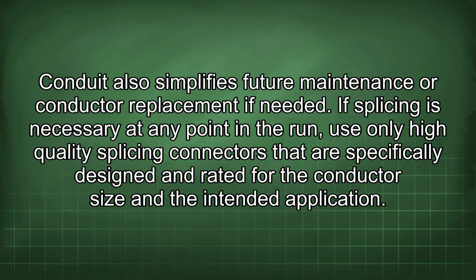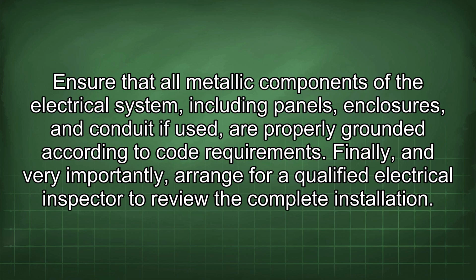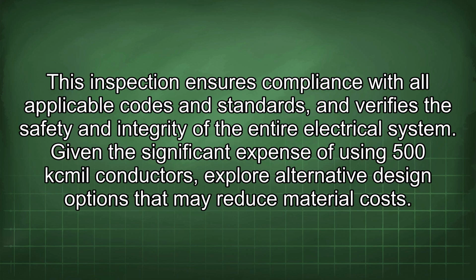If splicing is necessary at any point in the run, use only high-quality splicing connectors that are specifically designed and rated for the conductor size and the intended application. Ensure that all metallic components of the electrical system, including panels, enclosures, and conduit if used, are properly grounded according to code requirements. Finally, and very importantly, arrange for a qualified electrical inspector to review the complete installation. This inspection ensures compliance with all applicable codes and standards, and verifies the safety and integrity of the entire electrical system.